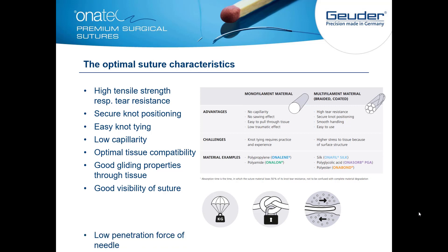For every suture task, there is a needle that penetrates tissue and leads the suture. One of the most crucial factors for sensible structures, especially in the eye, is penetration force. More force means the surgeon dents or buckles the tissue more. Therefore, minimal penetration force is the primary goal for every needle.